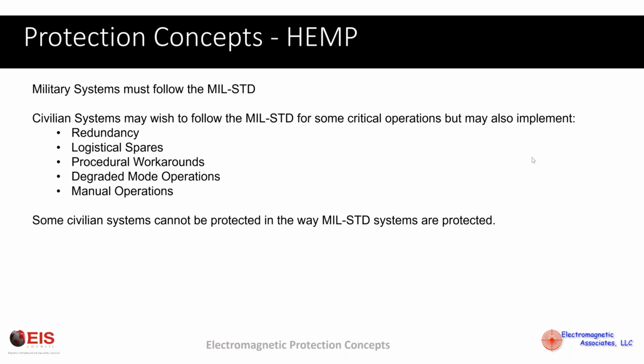For civilian systems, in some cases for critical operations, you're going to want to sort of mirror the MIL standard, but you should also look at other ways of enhancing your protection using redundancy and sparing. Maybe you have some procedures to work around when things fail. Maybe you have some degraded modes, manual operations. You should exercise all of these things so that they work the way that you expect them to. And indeed, some civilian systems you simply can't protect the way the MIL standard systems are protected. Like, you can't put a Faraday cage around the entire electrical grid.